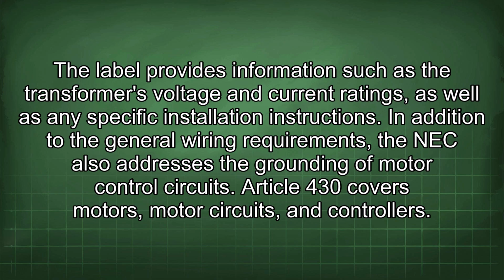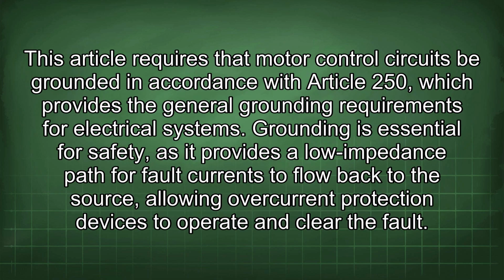In addition to the general wiring requirements, the NEC also addresses the grounding of motor control circuits. Article 430 covers motors, motor circuits, and controllers. This article requires that motor control circuits be grounded in accordance with Article 250, which provides the general grounding requirements for electrical systems. Grounding is essential for safety, as it provides a low impedance path for fault currents to flow back to the source, allowing overcurrent protection devices to operate and clear the fault.